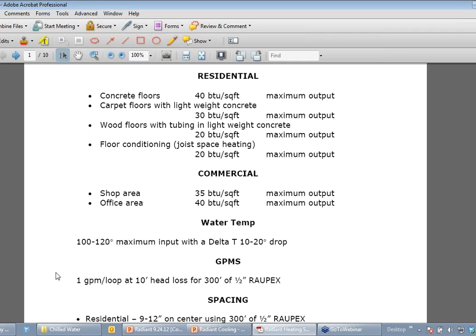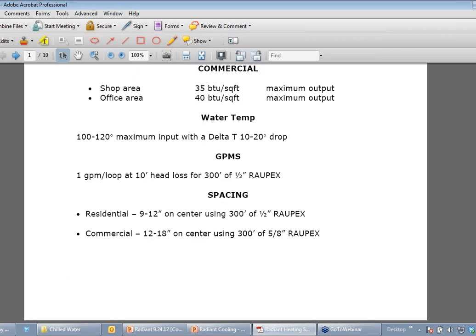In terms of flows, the general recommendation, if you're going to use half-inch PEX, which is very common. There's obviously larger and smaller sizes than that, but half-inch is one of the more common ones that we'd use. For example, if you had 300 feet of half-inch PEX, you'd have sizing for 1 GPM for each loop. Spacing residentially, we're typically doing about a foot apart is the most common recommendation.